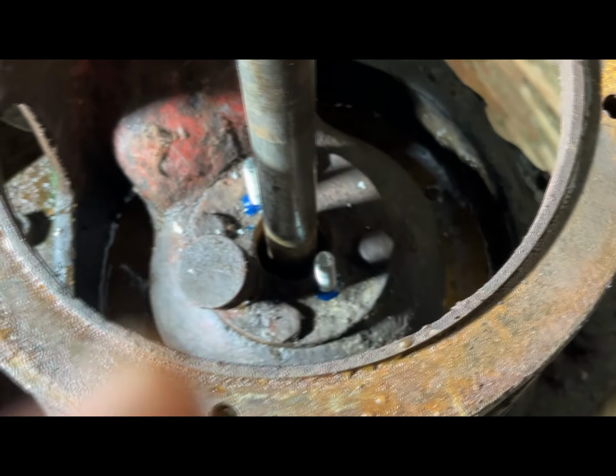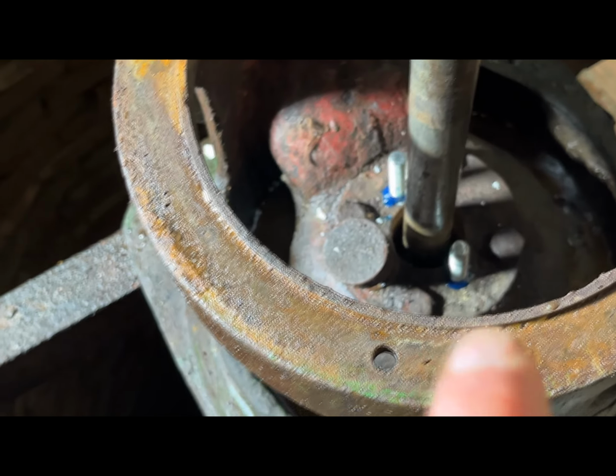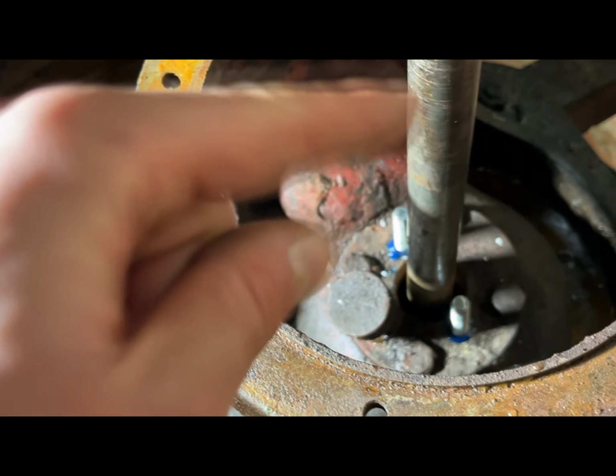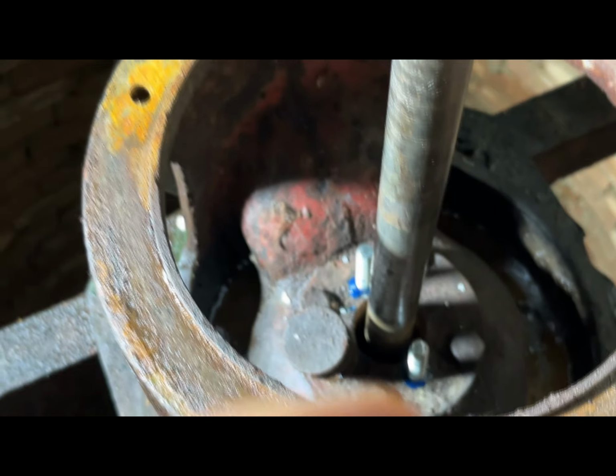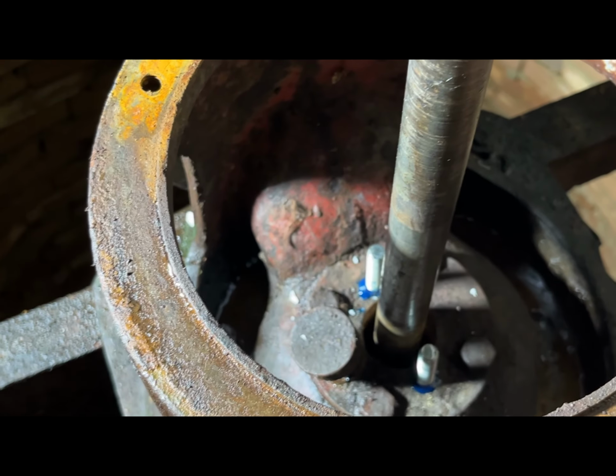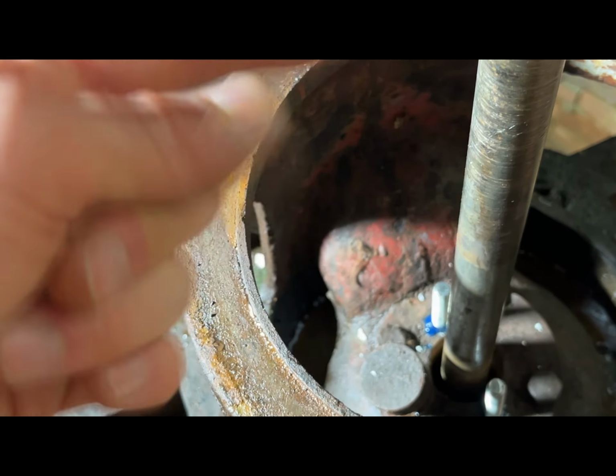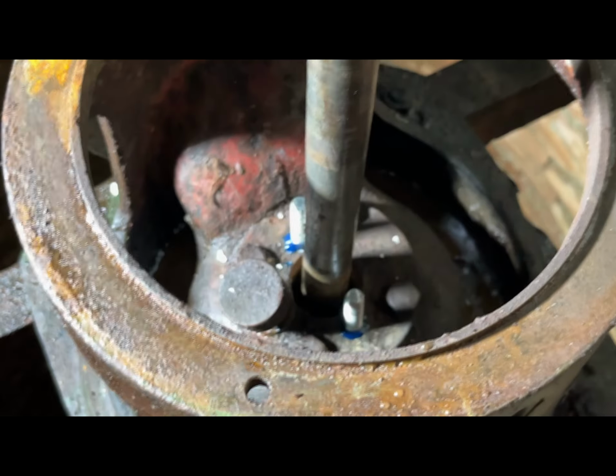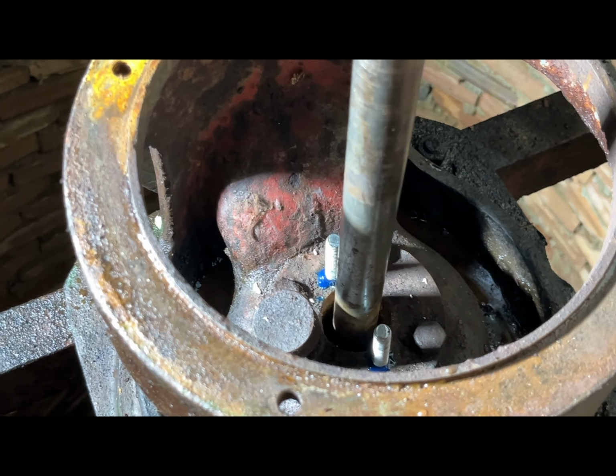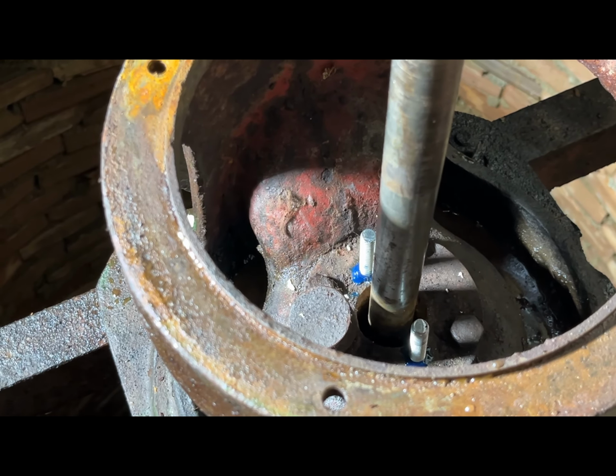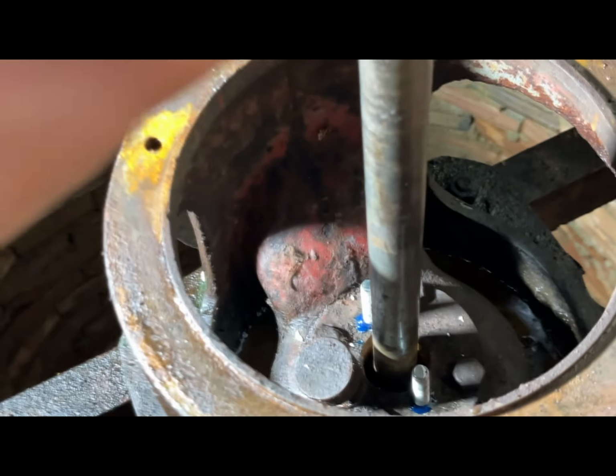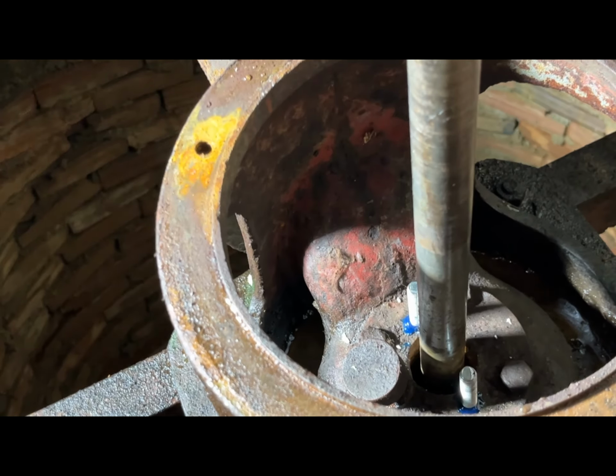After cutting your packing, you wrap it around and push it in, then take the gland and push it in even further. The next cuts you can do 90 or 180 degrees apart, so from this side to that side, which keeps the leakage to a minimum. Then you take your gland again and push it in further and further.